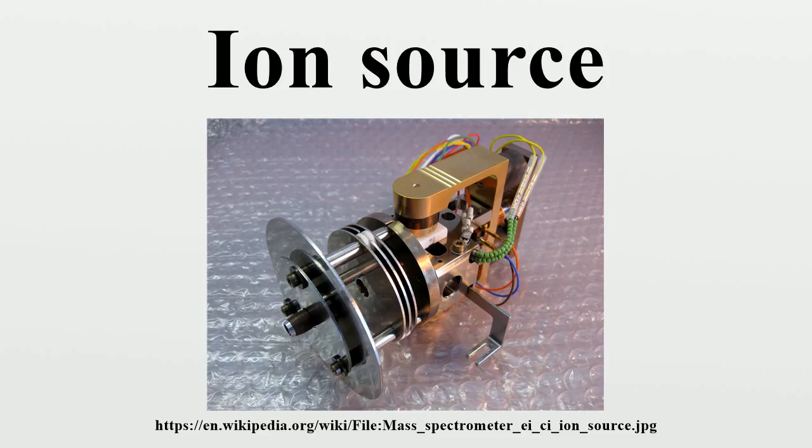Atmospheric pressure chemical ionization. Atmospheric pressure chemical ionization is a form of chemical ionization using a solvent spray at atmospheric pressure. A spray of solvent is heated to relatively high temperatures, sprayed with high flow rates of nitrogen, and the entire aerosol cloud is subjected to a corona discharge that creates ions with the evaporated solvent acting as the chemical ionization reagent gas. APCI is not as soft an ionization technique as ESI. Note that atmospheric pressure ionization should not be used as a synonym for APCI.